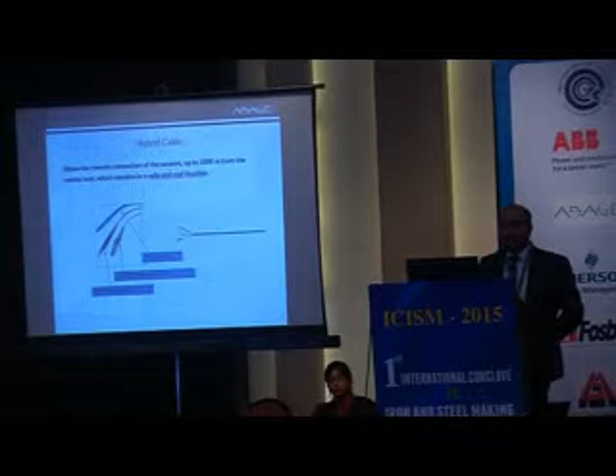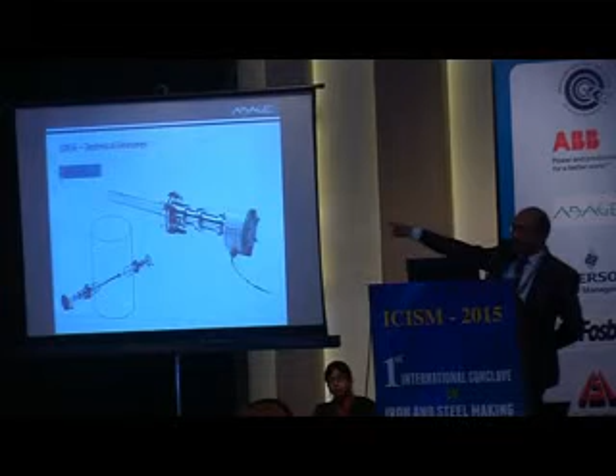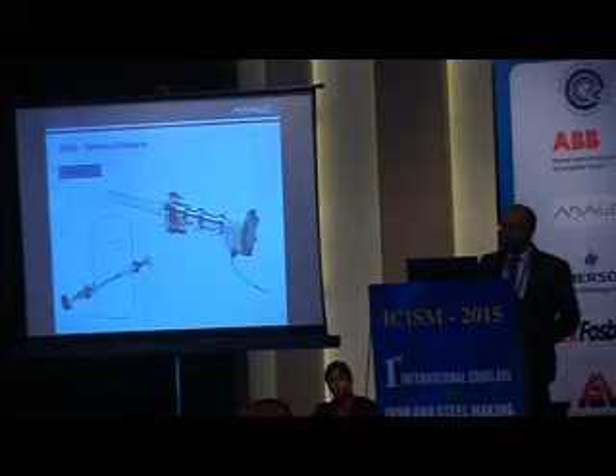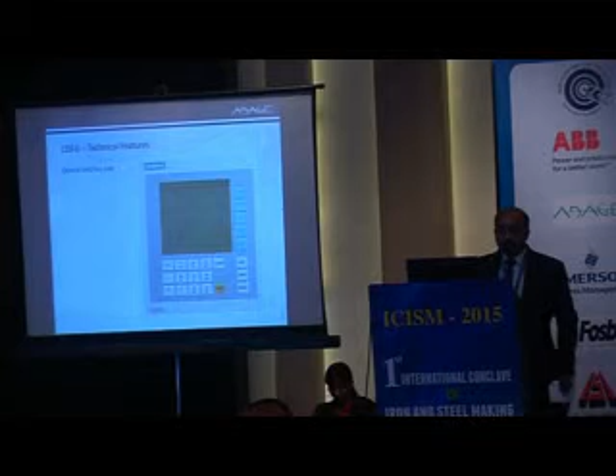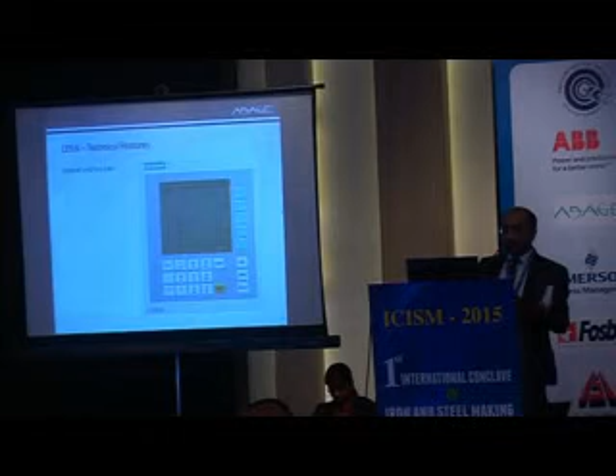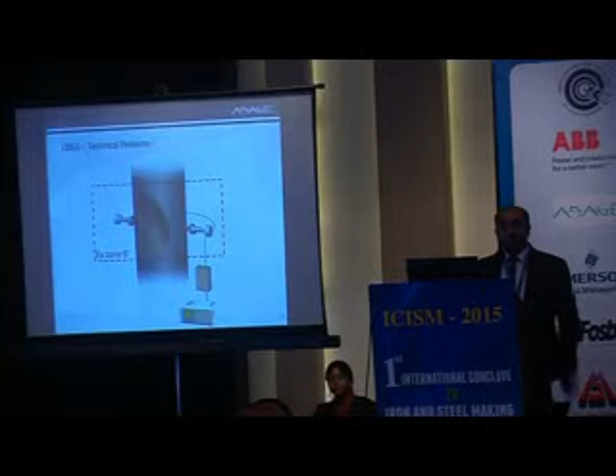And we have, of course, a hybrid fiber optic cable. And this is how it looks. So you have the sensor pairs, you can put them across your duct, your vessel, your stack, or wherever you want. And then, of course, this electronics which I'm talking about. You can even have this electronics put in your own chamber if you want to, because we do not bring gases. So there is no need to make a separate analyzer room, bringing the hazard of dirty gases or hazardous gases inside. You can even have it in Ex zones.